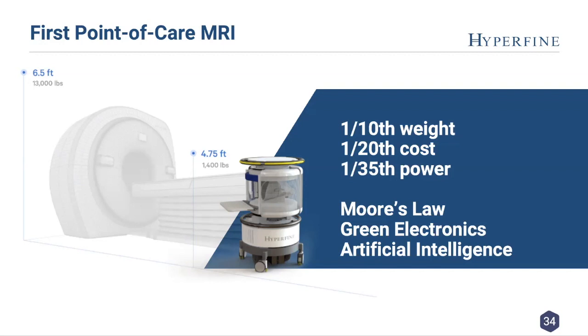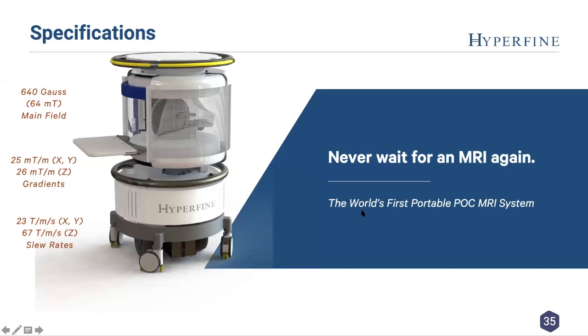I know some of you are interested in technical specifications, so I put a few here. It is 64 millitesla, a 640 Gauss static field. The gradient performance, which I think is amazing coming from a 110 volt power outlet, gets 25 millitesla per meter on the X and Y axis and a little more on the Z. Our slew rates are respectable, so we're able to do diffusion weighted imaging - B values of 800 right now, and soon B values of 1,000.